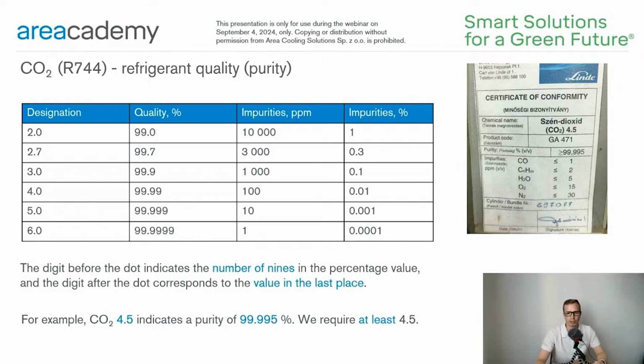In CO2 systems, the purity of the refrigerant plays a big role. To understand the information about the purity of the refrigerant, which is given on the cylinder's sticker here, let's analyze the table. For example, the 2.0 purity means that the quality is 99.0%. The digit before the dot, the 2, indicates the number of nines in the percentage value, while the digit after the dot corresponds to the number in the last place of the percentage value. The purer the CO2 refrigerant, the better its thermodynamic properties, and the higher the efficiency of the system. We recommend using CO2 with a purity of at least 4.5.